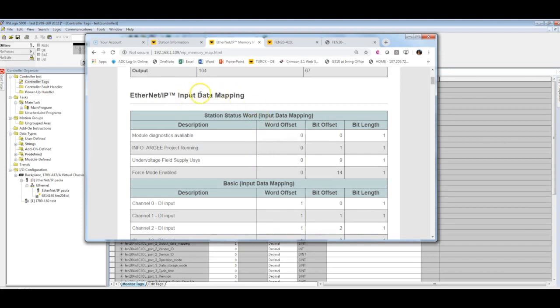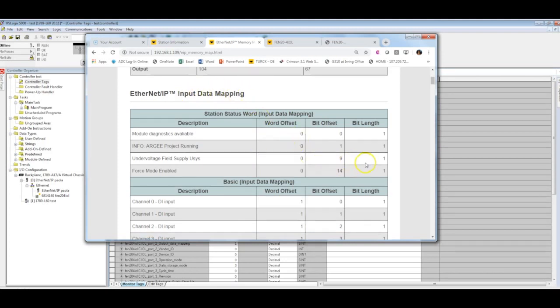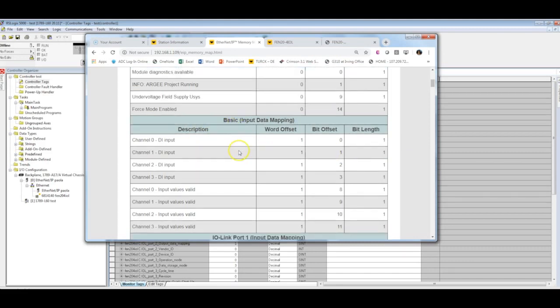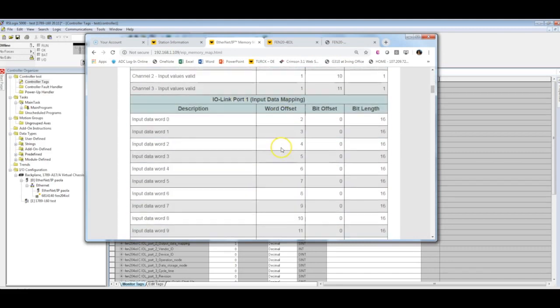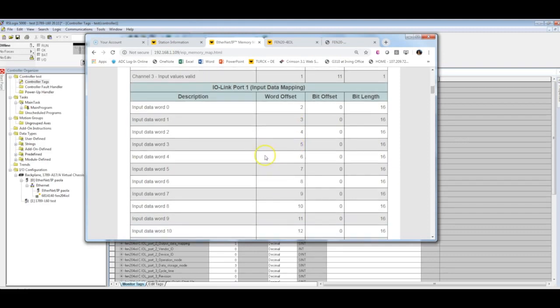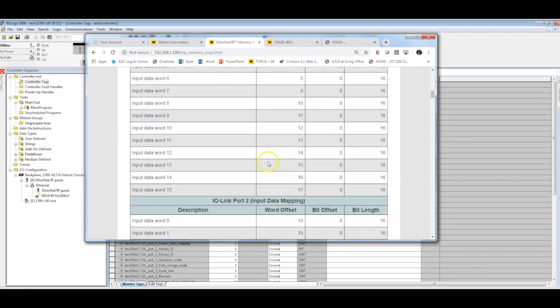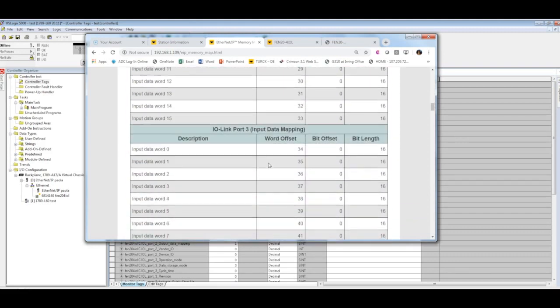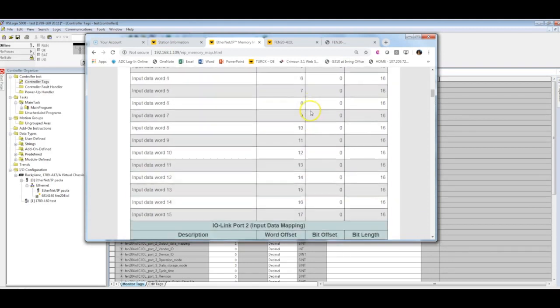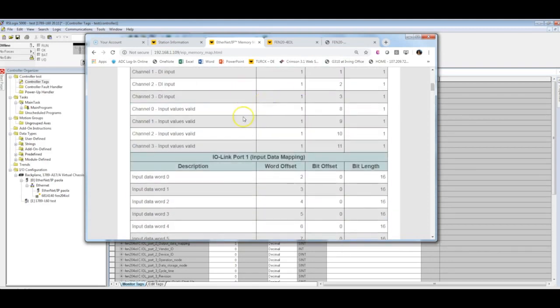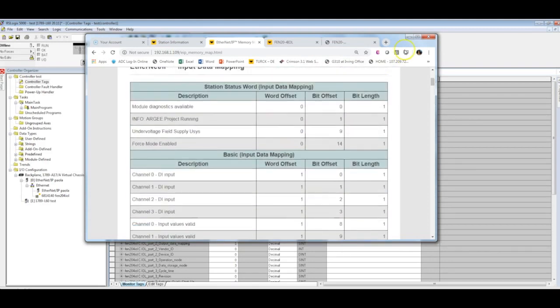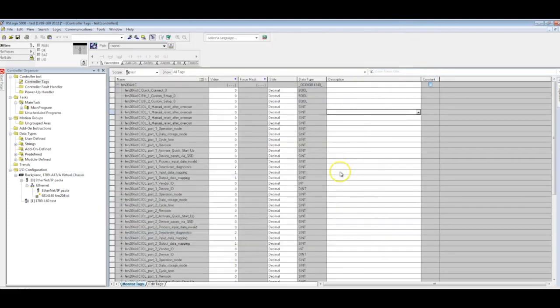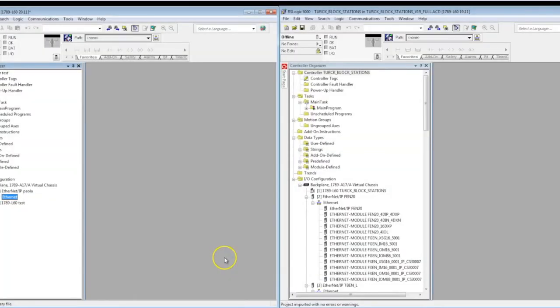What I would recommend in this case is going to your internal web server and go ahead and look at the input data mapping here. If you are doing everything over the EDS file, this will give you a general idea of what words mean what and how everything is distributed. So this can help you. You may not be using a lot, so it might not be a big deal. But this is one way of adding a Turck block into your existing RSLogix 5000 project.